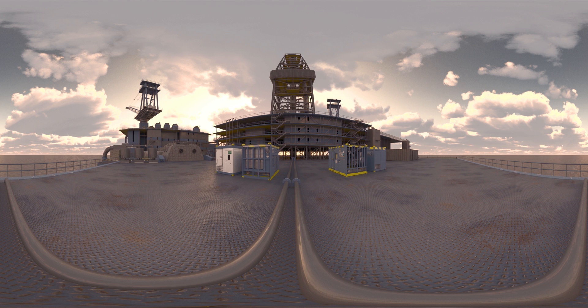Rig-safe areas, often identified as permanently safe, tolerate the use of low protection equipment. Zone 2 areas may contain hydrocarbon and require high protection equipment for operation within hazardous environments. Catastrophic failures such as line rupture are not considered by an area classification study. A hazard identification process such as HAZOP should consider these events.